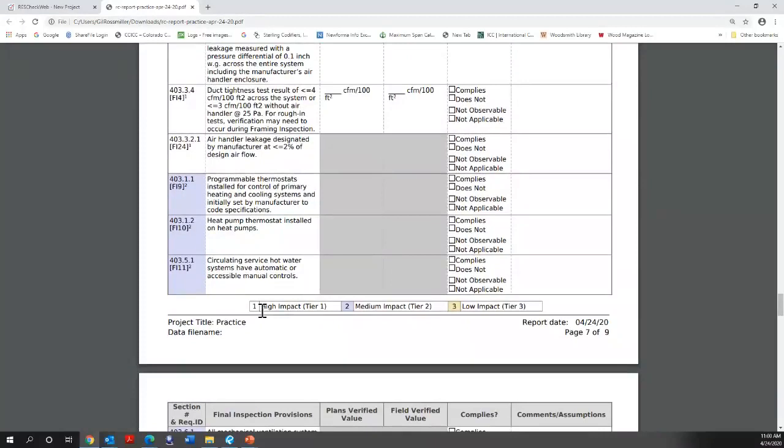Well, the most common mistake is that they're not in the construction plan. That's probably the biggest mistake, that when I look at the construction plans, they're either not clear on what is supposed to be installed, or another thing that I don't like is they'll say, see REScheck. No. Nine times out of 10, nobody knows what a REScheck is, right? It's got to be on the plans. I don't see square footages mucked up a lot. Typically, it's pretty rare when I find that they haven't included the second floor walls, for instance. I'm looking for big mistakes, not little mistakes.